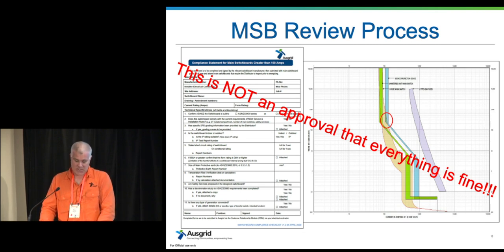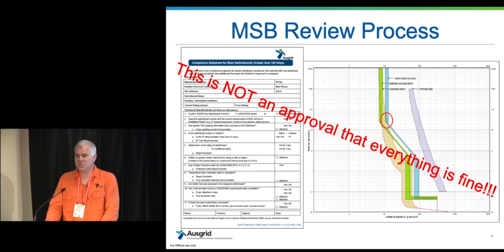I can't stress enough, when we shook the tree for 3439, merging over to 61439, it was pretty disappointing how many switchboard builders could not prove their compliance to 3439, let alone to 61439. I even had one switchboard builder tell me, not in this room, that it was industry practice, and that absolutely blew me away. I was expecting a handful of people, not a significant percentage, to come out with these outrageous claims. I pretty quickly bit back and said, well, what's industry practice? Is industry practice committing fraud? They said, what do you mean? I said, you've put a label on the front of this switchboard saying it complies to 3439, but you can't actually tell me that it does. You can't prove that it does.